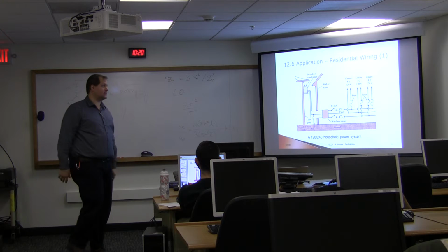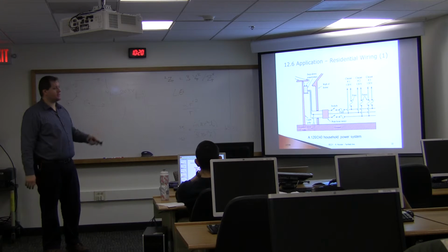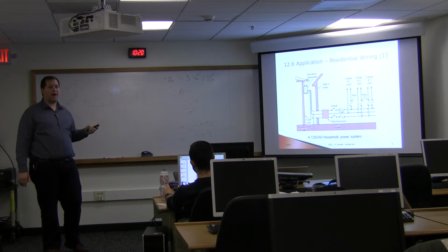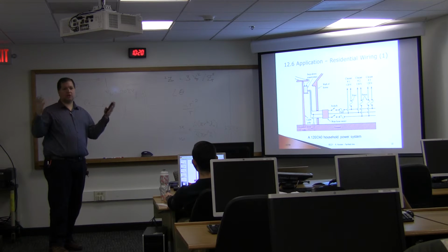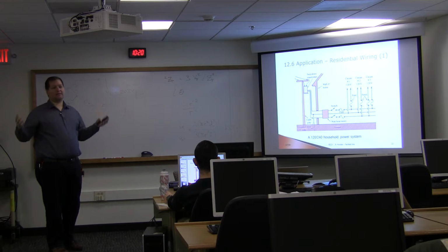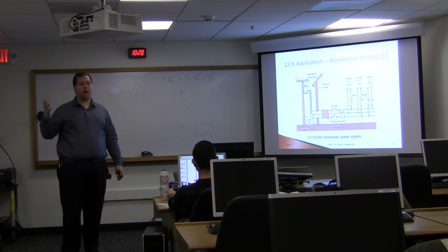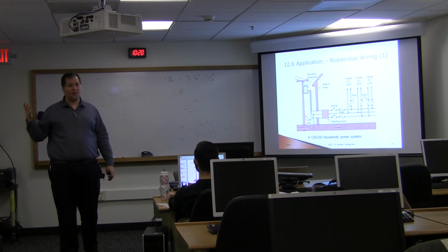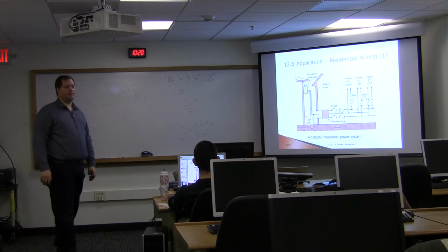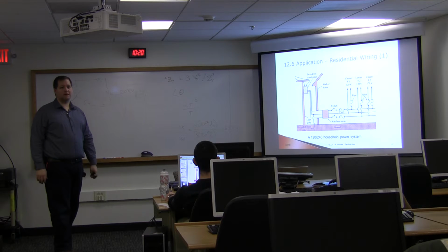Why is that? Normal circuits are wired with 12 gauge wire, which can carry maybe 15 amps of current, so you put it on a 15 amp breaker. An incandescent bulb—if you put in 10 100-watt bulbs, you'd burn 1,000 watts of power, which on a 120 volt system is somewhere near 10 amps. That starts to get near the limit of the wire, so they say that's enough, building in a bit of a safety factor.